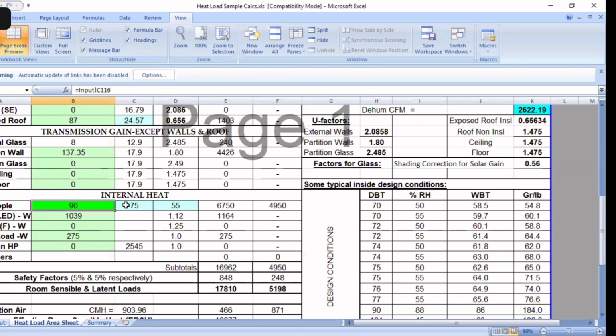People 90, 75 watts sensible heat per person, 55 watts latent heat. This is the total for the 90 people. This is the sensible heat. This is the total latent heat for 90 persons. LED light, I have taken the value from the input sheet, multiplied it by area. Input has given watt per meter square, from there it is the area. And lighting load has come. Then equipment load I have considered 275 watt approximately.